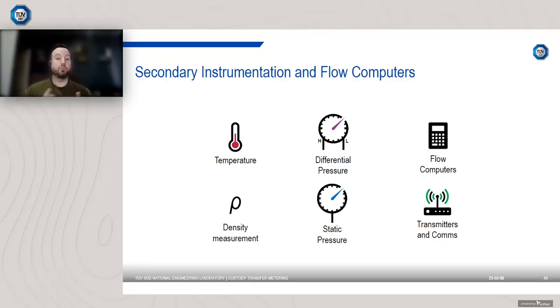Temperature and pressure measurement are really important for determining things like fluid properties. Density measurement can be important depending on the metering technology you've selected, in order to determine the mass of the fluid. Differential pressure again is critical, especially if you've selected a differential pressure flow meter. You need to measure the differential pressure. You've got various different transmitters and communication types, and flow computers are another critical component. So I'm going to talk a little bit about each of these just to finish off the webinar.